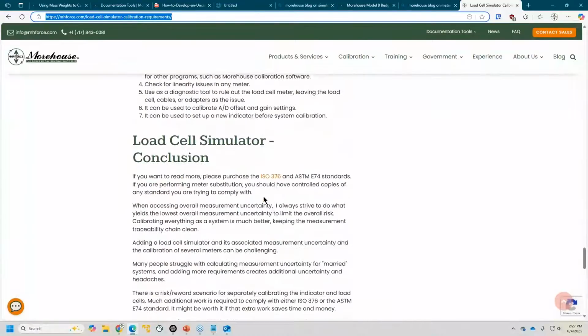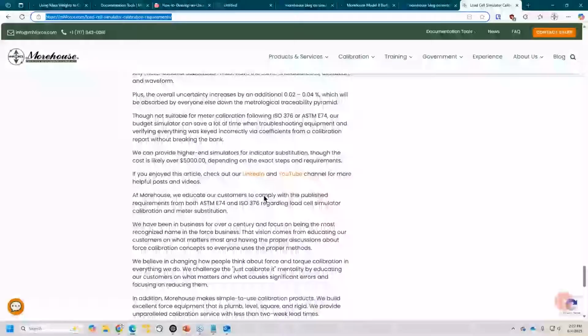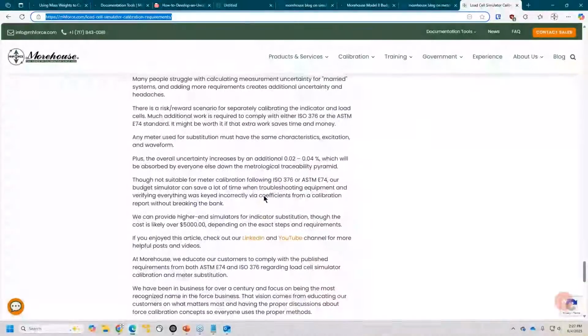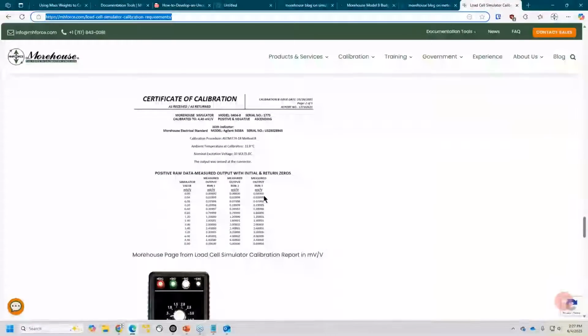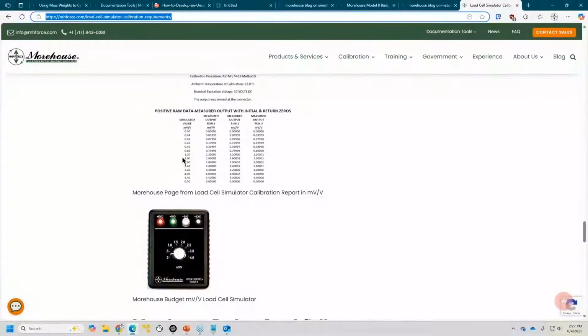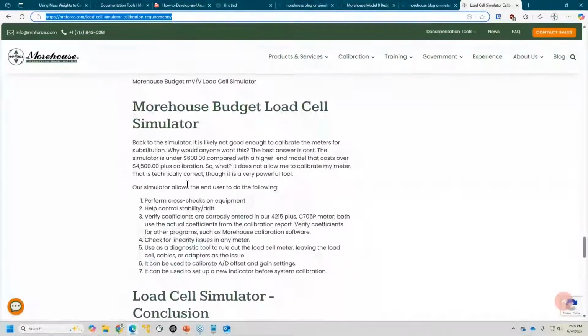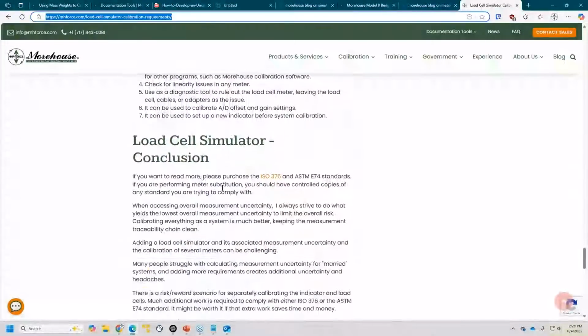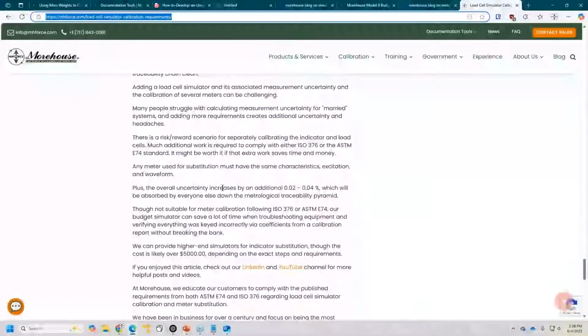They have a first force point simulated load that allows you to do low points, because of the caveat in ASTM, and there's a sort of simulator cal. I think our new simulators will go down to 0.2. What ASTM basically says is when you do substitution, you have to do the full range. So this limits you, and that's what I'm explaining. Some out there are about 4,500, and 600 for the pretty cheap one.